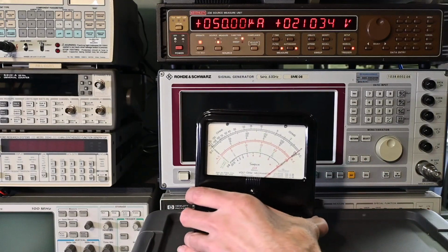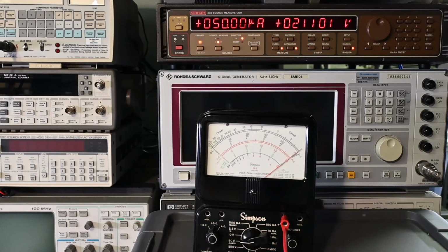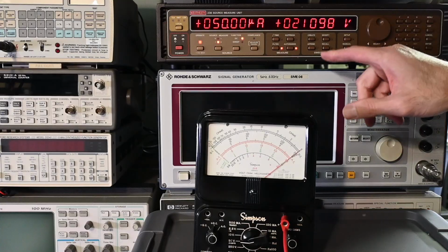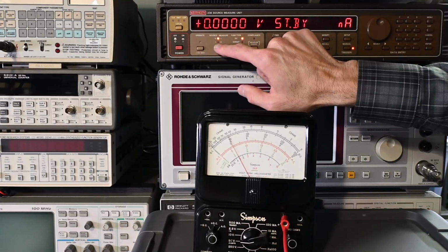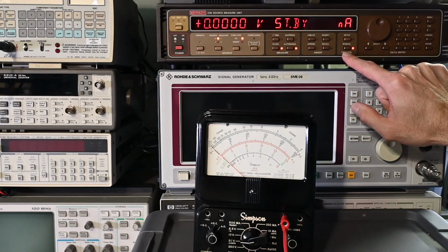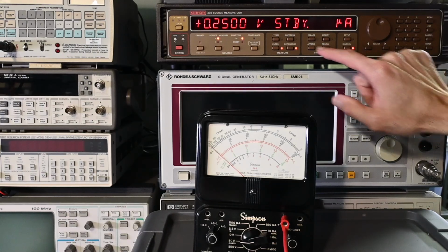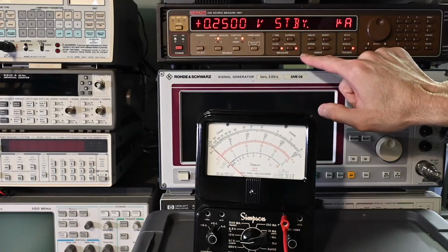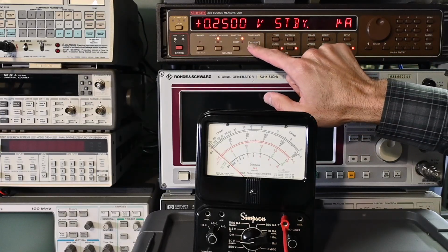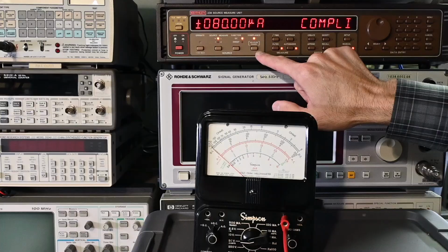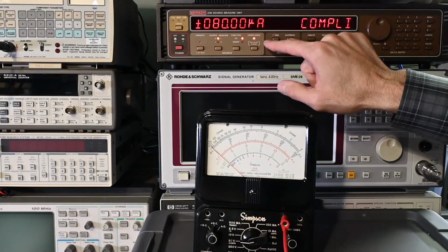Also keep in mind that the first calibration for the DC adjustment that I was showing you needs to be done only with a constant current source, not a constant voltage source. If you try and do that first calibration with a set voltage, it won't work correctly. So keep that in mind when you're doing these calibrations. So let me switch this over here to turn this off. Let's go to constant voltage. And let's double check this here. So we're on 250 millivolts, and compliance is on 80 microamps just for safety. So that's fine.